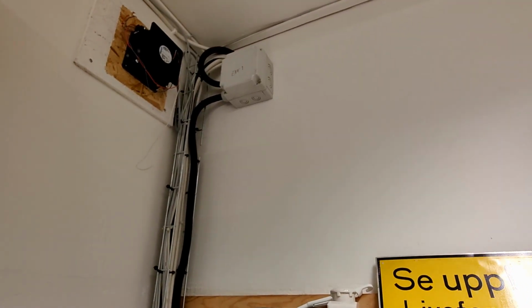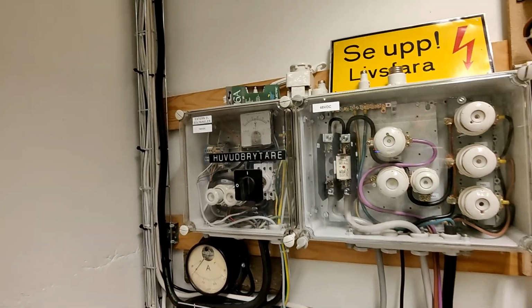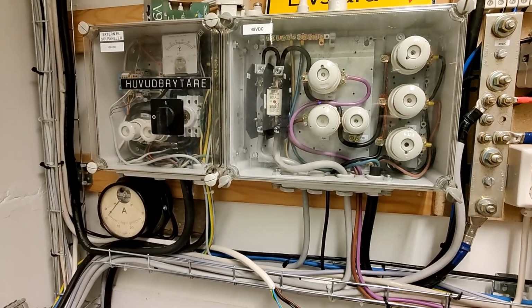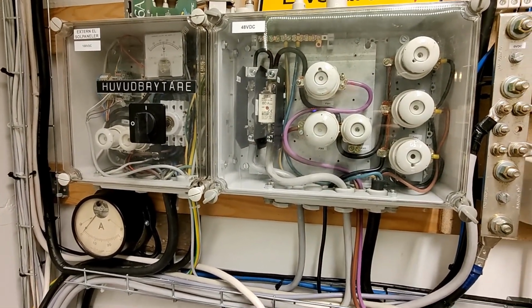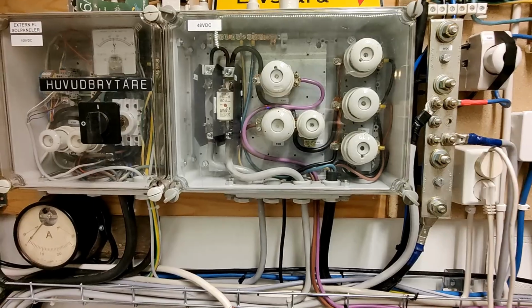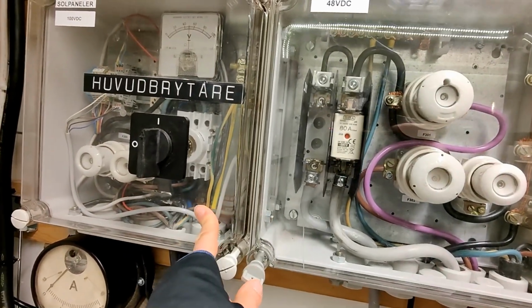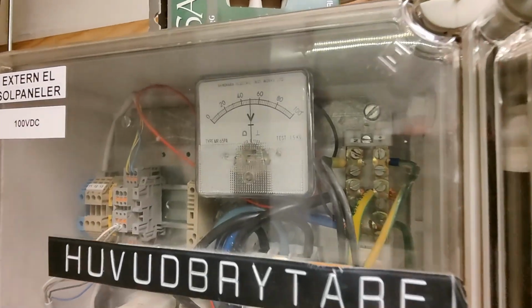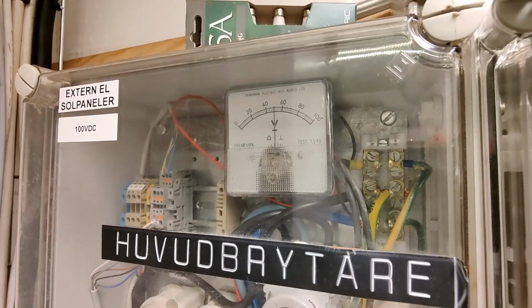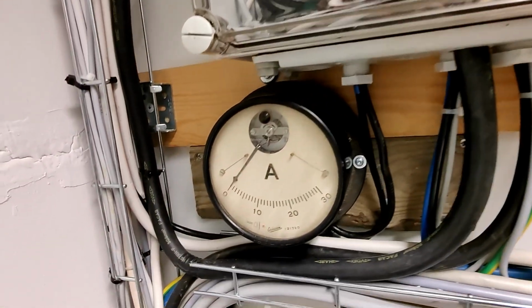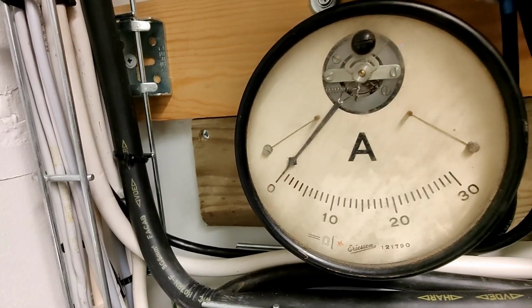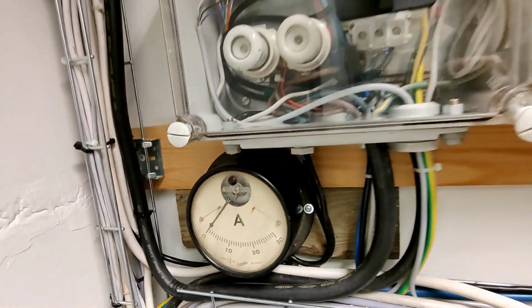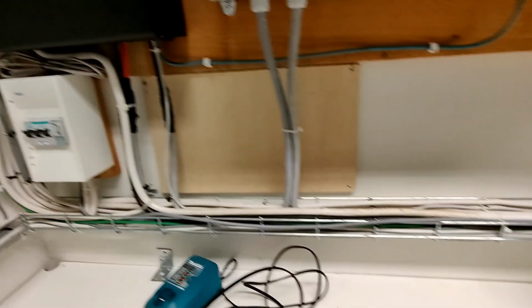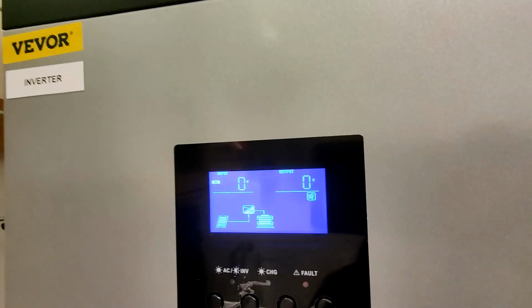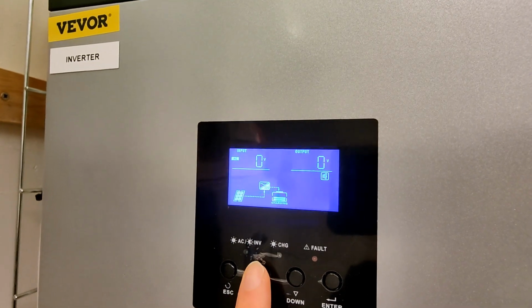Here's the other side of the wall where the cables came in. There's a battery compartment. We have this 48 volt backup battery system here. The solar panels go in here. We have some voltage, but there is almost no current. Got this amp meter here from the solar panels. And that feeds to the inverter. It tries its best to charge the batteries.